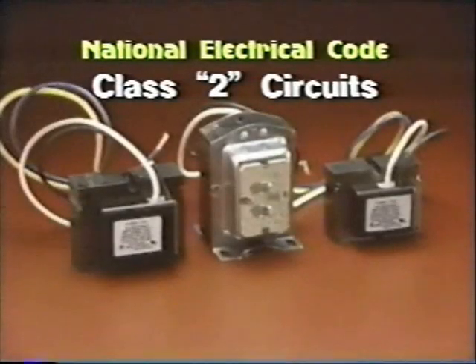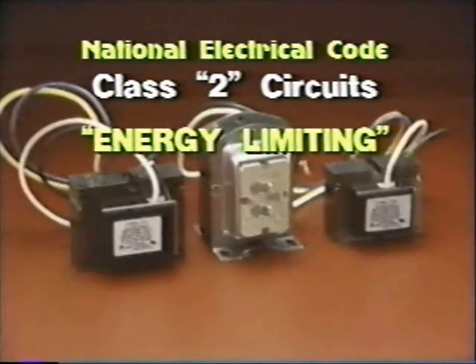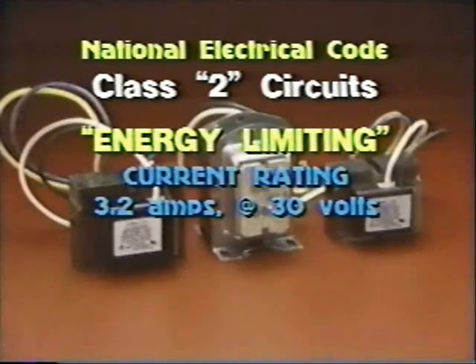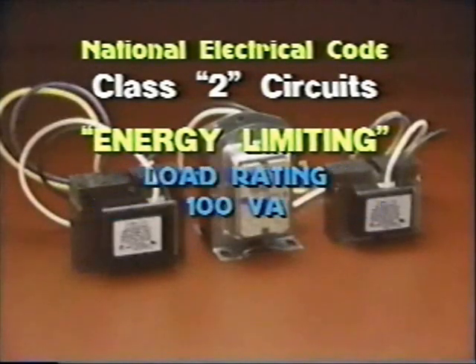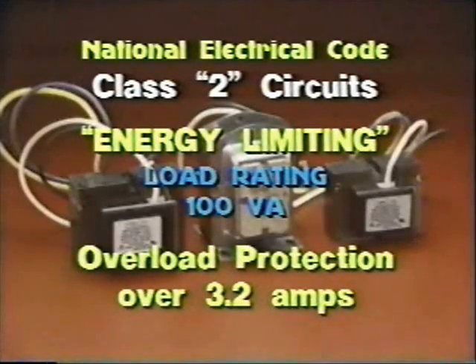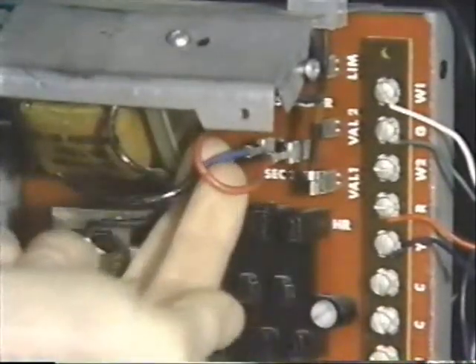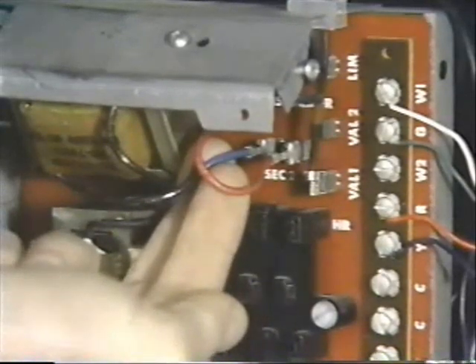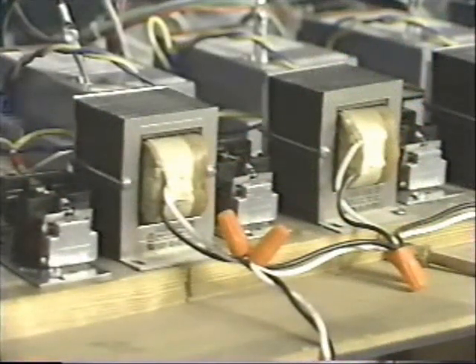Class II circuits, as defined by the National Electrical Code, are energy-limiting circuits. The maximum secondary current load is 3.2 amps at 30 volts, and the maximum load rating is 100 VA. If the circuit draws more than 3.2 amps, a fuse must burn out or some other type of overload protection must stop the flow of current. The major advantage of a Class II circuit is that it can be safely wired at very low cost. Thermostat-type wire can be used, which is considerably easier and less expensive than running conduit. In addition to meeting the NEC code, Class 2 transformers must pass a burnout test to meet UL safety standards.